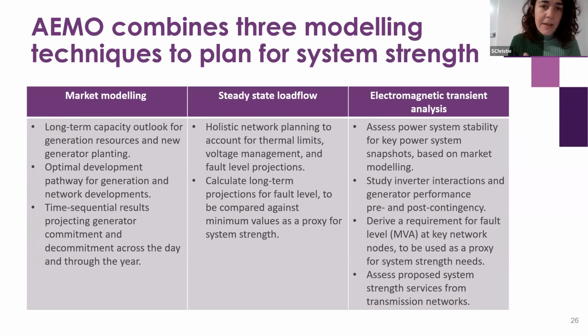However, we are very cognizant that fault level is a proxy only for system strength. It is nowhere near precise enough to anticipate the needs of the system and the interactions between all the different devices on the system. So a large amount of our analysis for what is needed for system strength and what will keep the system secure is done through electromagnetic transient analysis.